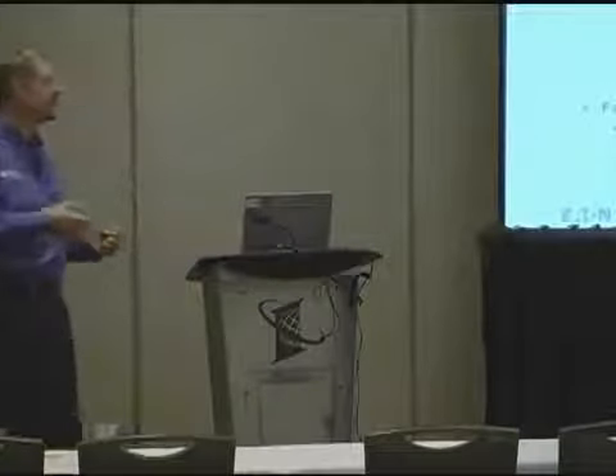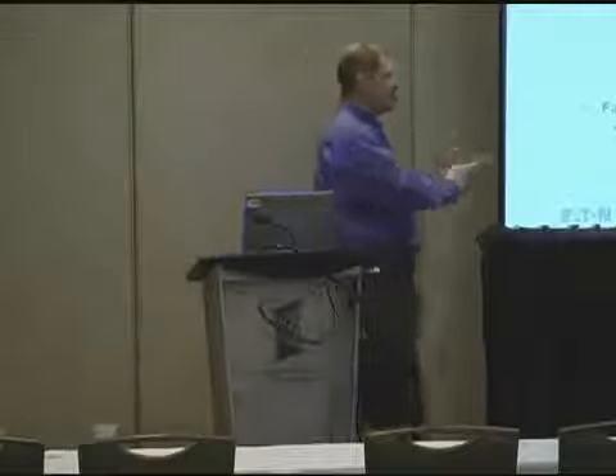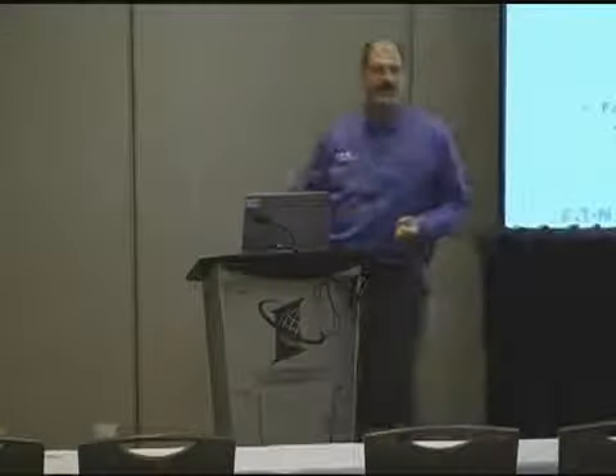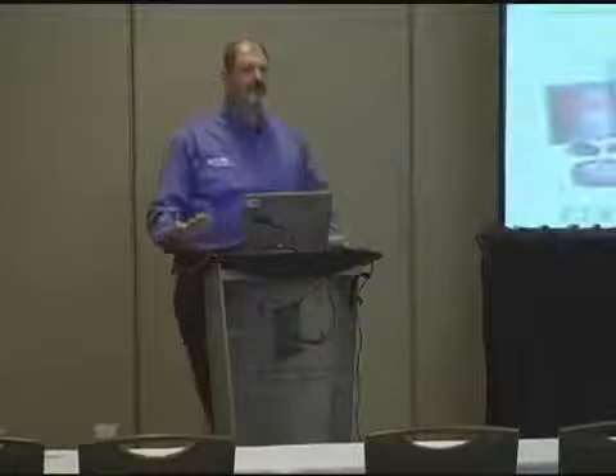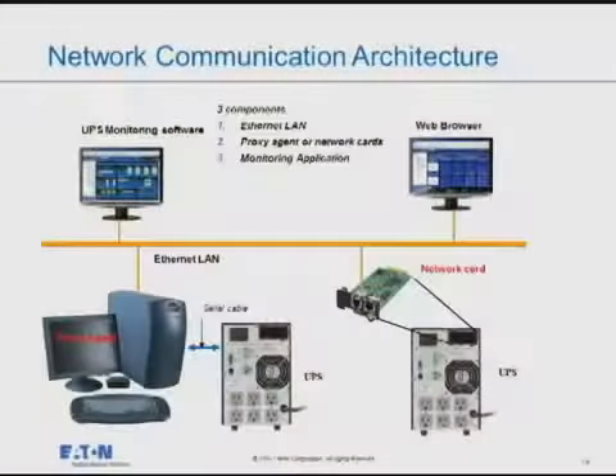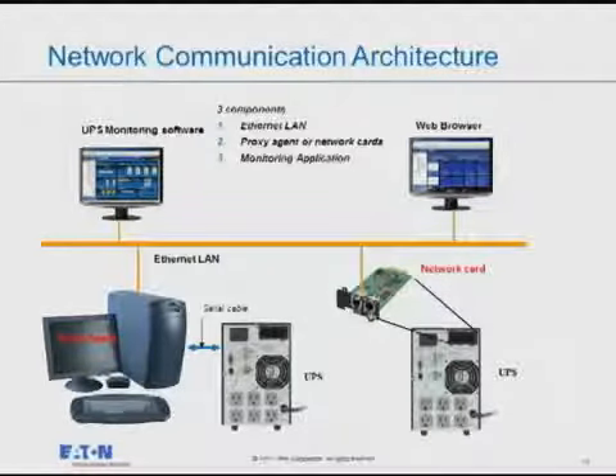So it's a different kind of world from the facilities, which has traditionally been Modbus TCP/IP talking to a Siemens or Honeywell or building management type of system. What the UPS does is bridge that gap between the two. Once I put the UPS onto the network and give it an IP address, I can communicate to the different worlds and interoperate across them.